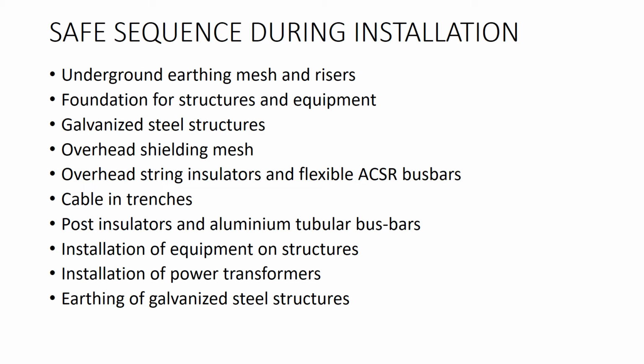Installation should be planned and executed under the guidance and supervision of experienced personnel. So the preferred sequence of installation is given here as an example for an outdoor switching yard. The underground earthing mesh and risers should be the first. Maybe the second one, the foundation for structures and equipment, can be done parallelly. After completing these two works, that is underground earthing mesh and foundation structure for the equipment, that is transformer and other circuit breaker and all.